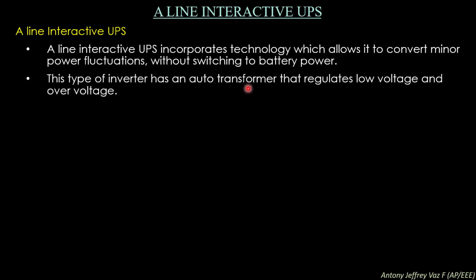The line interactive UPS has an auto transformer that regulates low voltage and over voltage. When there is a low voltage, the auto transformer operates in step-up mode to deliver the correct voltage to the connected device. When there is a high voltage, the auto transformer switches to step-down mode so that the correct voltage is provided to the device connected at the output of the UPS.